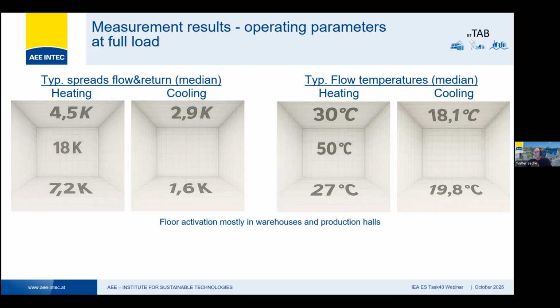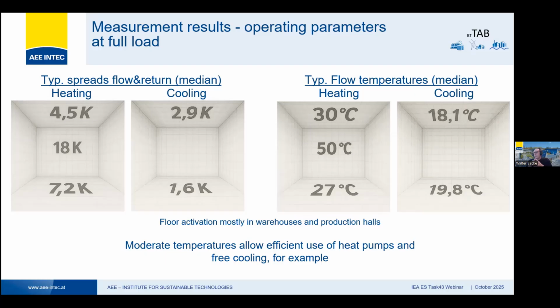And if you look on the very right side, you see the typical flow temperatures for heating and cooling. In all cases, it was free cooling or passive cooling. So you just use a borehole or a ground collector and run the temperatures coming out there through the tubes. And in all cases we have quite moderate temperatures, on the heating side and on the cooling side. And there's this connection between the temperature differences and the moderate temperatures. The big advantage of those moderate temperatures is that this allows an efficient use of heat pumps and free cooling or solar thermal. So basically renewable heat and cold.